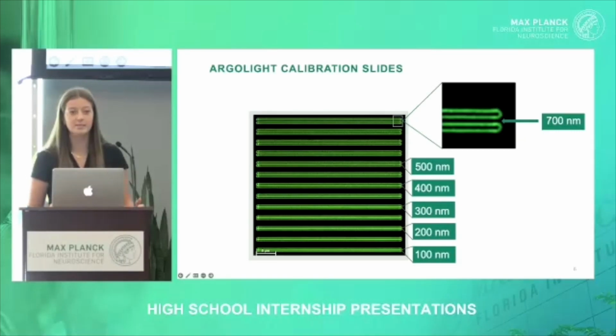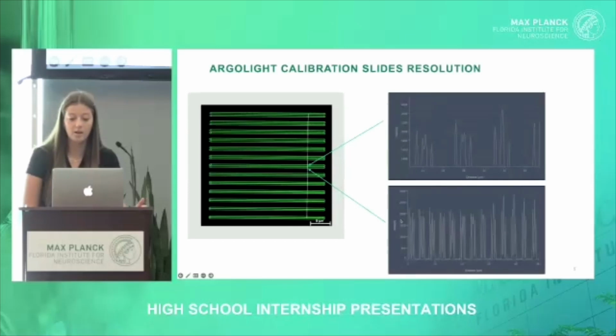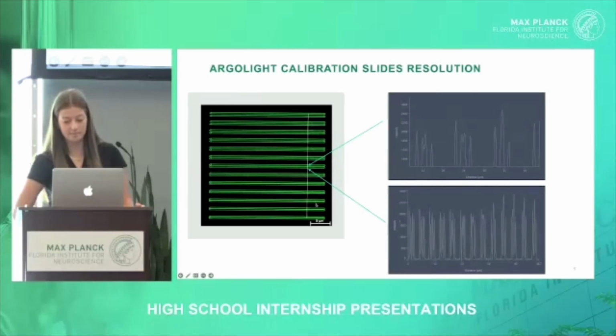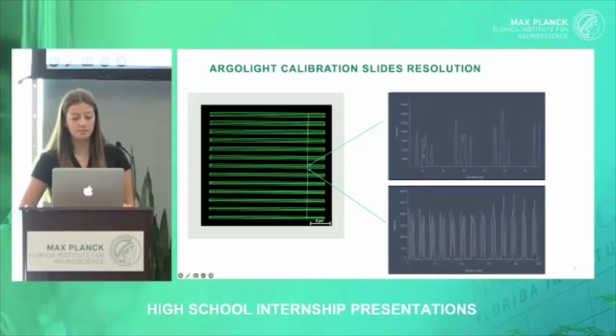Since these exact distances are known, by observing the images of these slides and finding where the gap between the lines is no longer visible, I can tell what the resolution of the image is. The resolution can be mapped by a line intensity profile. So these graphs show the intensity of light at each point on this line. The peaks on the graphs are the areas with the most light signal, and the dips are the black spots that the line passes through. So the resolution of the image can be mapped using these peaks, because when four peaks turn into three, there's no longer any visual separation between the lines, meaning that is as far as the image is resolved.